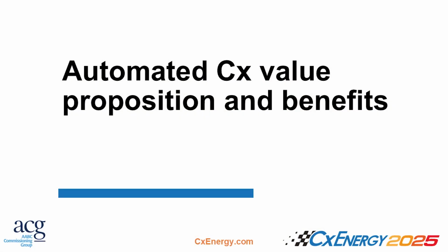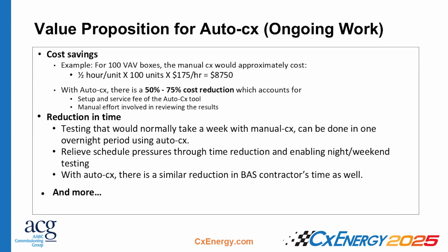So I talked about value proposition at the beginning, in the intro. We're talking to partners right now about how to best characterize the benefits of automated commissioning. One big thing that's come up is this idea of cost savings, right? So if you take an example of 100 VAV boxes, we hear the rule of thumb is about half an hour to test a VAV. If your customer has 100 units, and we multiply that by a rough $175 per hour, you're looking at $8,750 for the whole 100 VAV boxes.